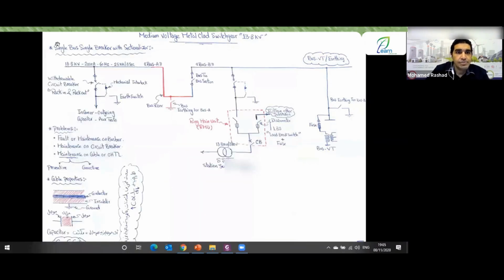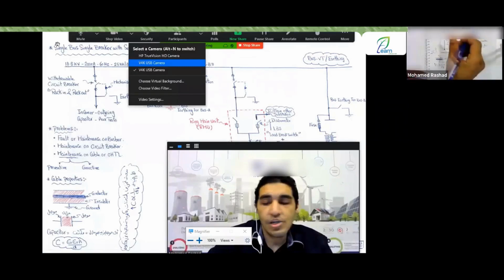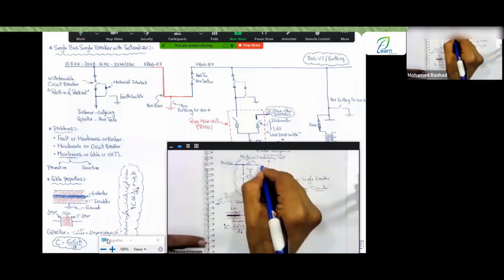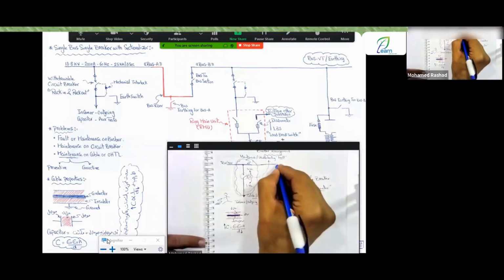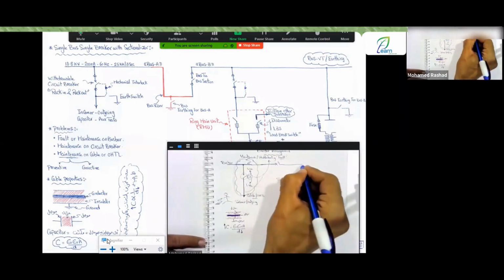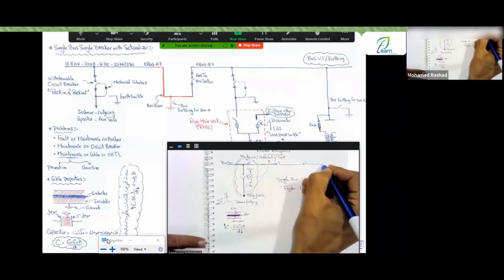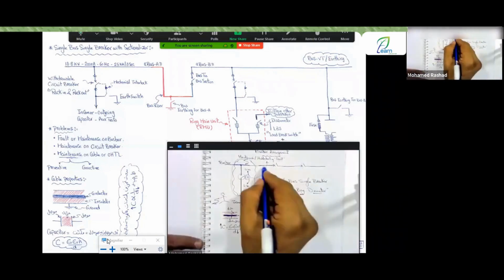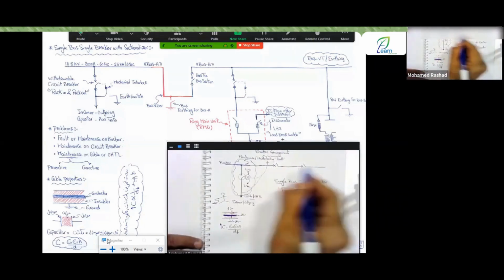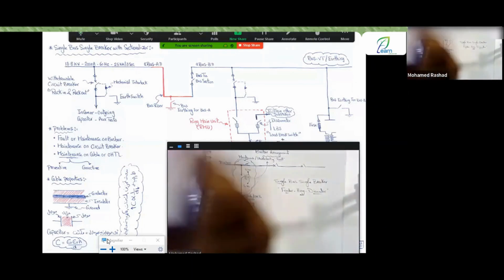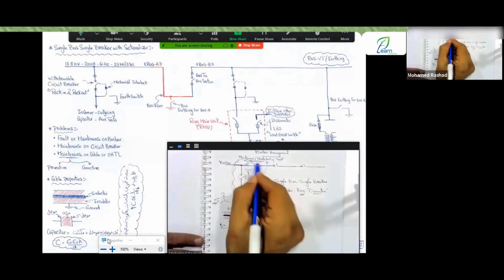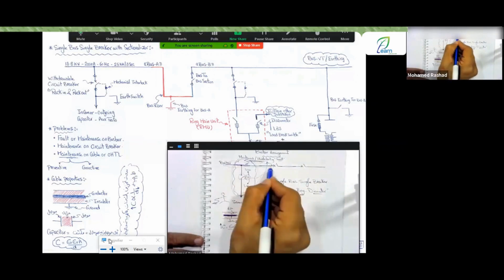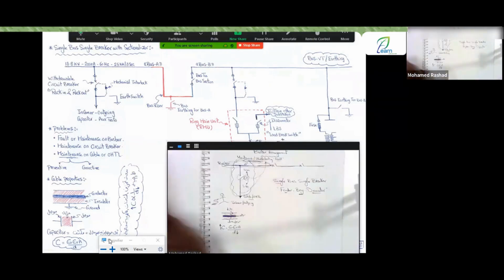And we operate here like this and activate the circuit breaker for you. All right, so as an engineer here, you will have this setup where you bring another bar and move like this, then a 3rd bar and move like this and so on. All right, so this is the 1st bar, this is the 2nd bar, and this is the 3rd bar. So you have divided the same bar. Therefore, if you have maintenance or troubleshooting on this bar, you only need to shut down 1/3 of the station instead of the entire station, right?